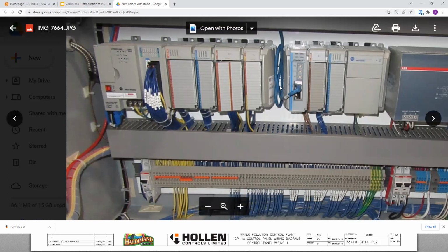These do not connect back and forth. So you can see here that these cards slot in the top. These little white tabs will actually positively slide over into the card to the left of them. And this chassis is complete. So if my memory serves me correct, there's a limitation with this family of processor where the power can only supply 4 cards to the right of it. After that, you have to end the chassis.